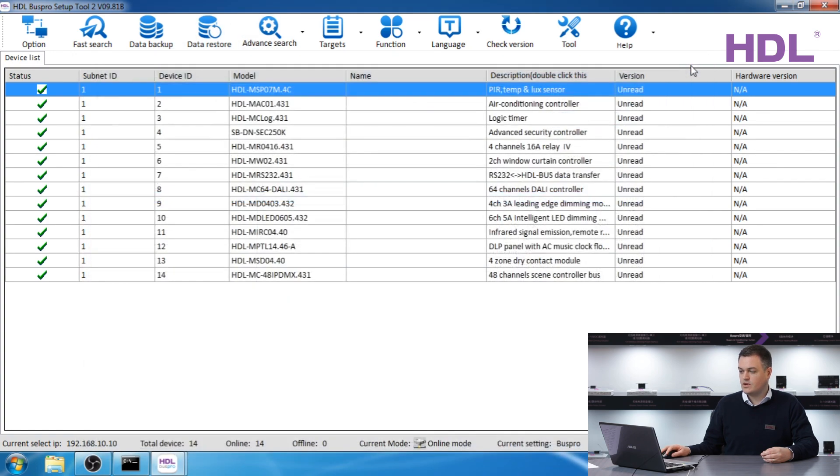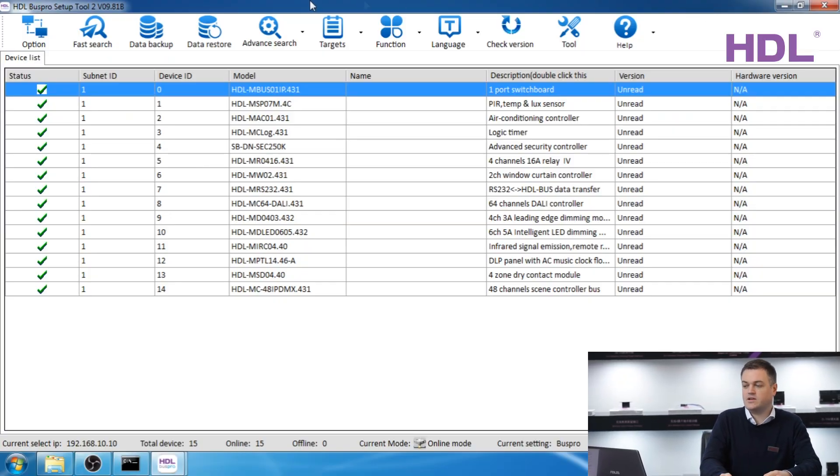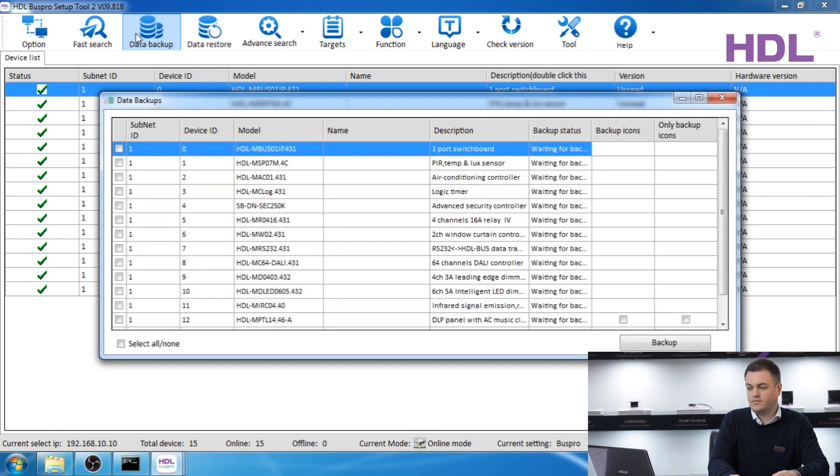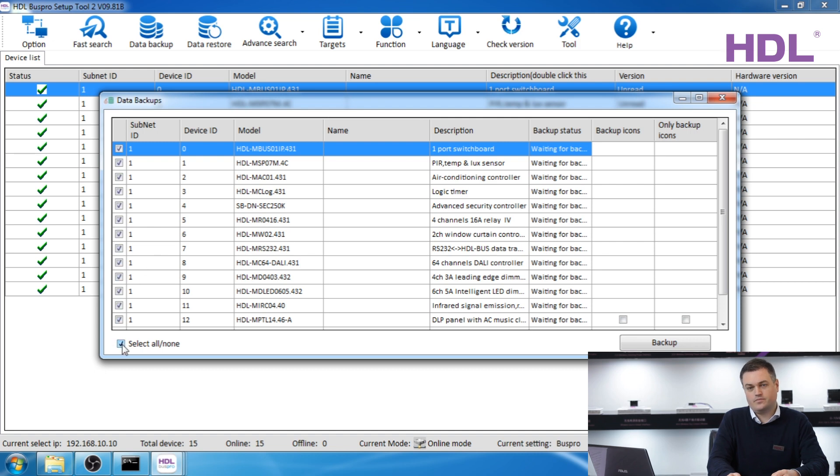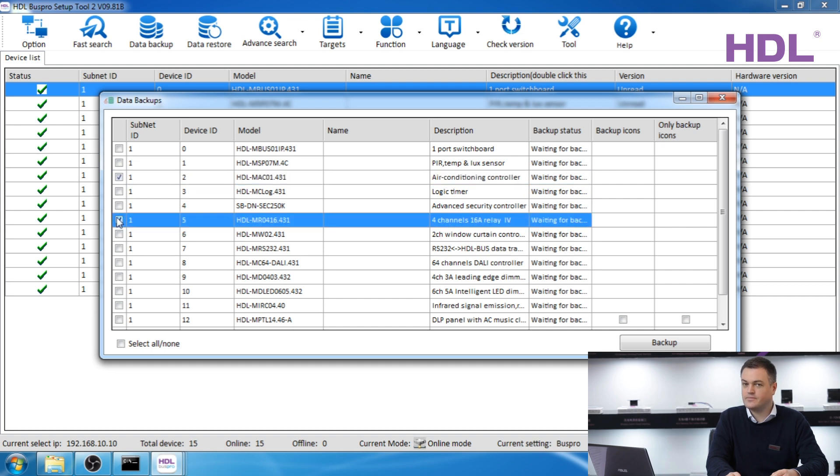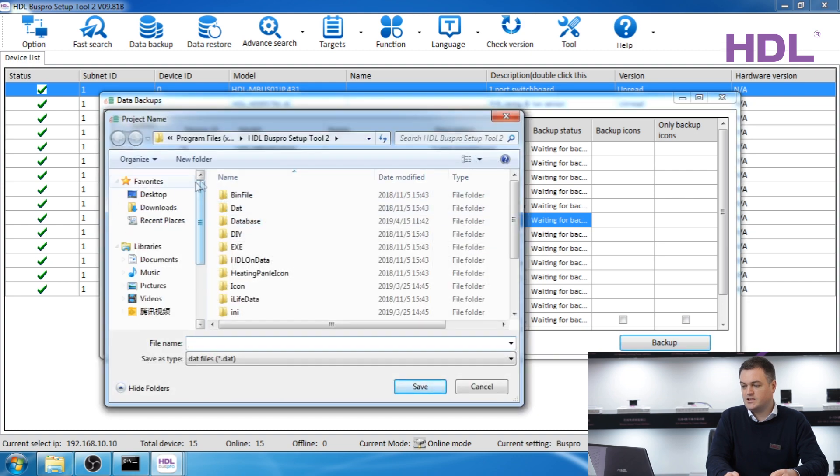Now I'll show you the way that you can back up all of your devices safely to the PC. This can be done once you have finished programming so that you can take a backup, or it could be used to back up and restore to several systems the same, for example apartments or hotel rooms. To do this make sure you have the devices on your screen and click data backup. Next you can tick all of the devices you would like to back up. For this example we will just tick two devices, air conditioning module and four channel relay. Click backup and select a folder.